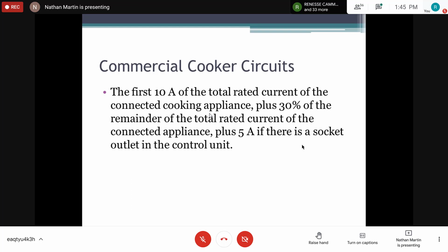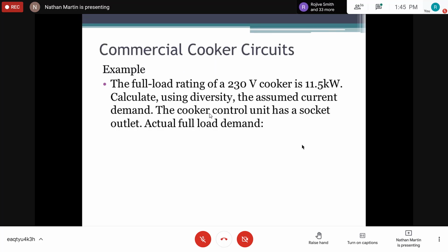So what does all of this mean, right? In doing this calculation, for example, the full load rating of our 230 volt cooker is 11.5 kilowatts, right? Calculating using the diversity factor, the assumed current demand, the cooker control unit has a socket outlet, actually full load demand, right? So this is what we will do: we will find the demand current. So we say the demand current of the device at full load is 50 amps, right?